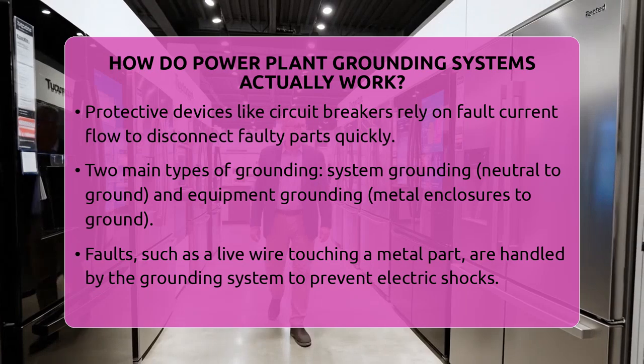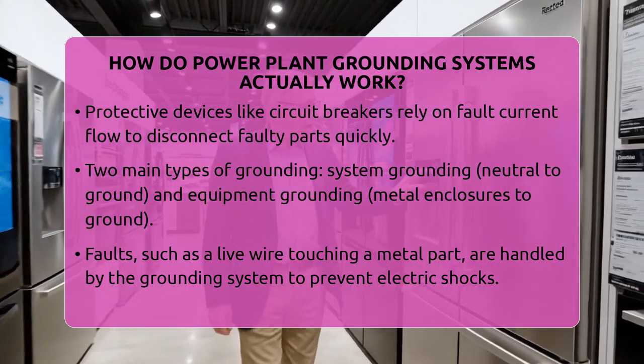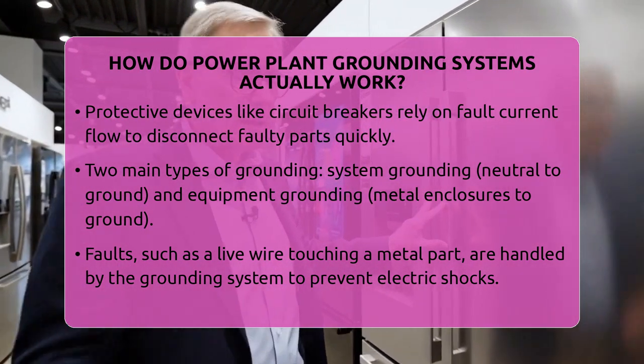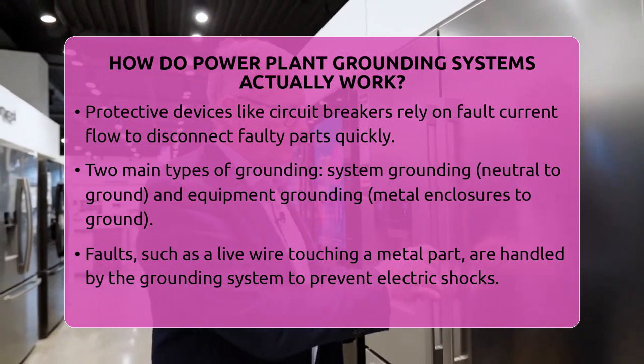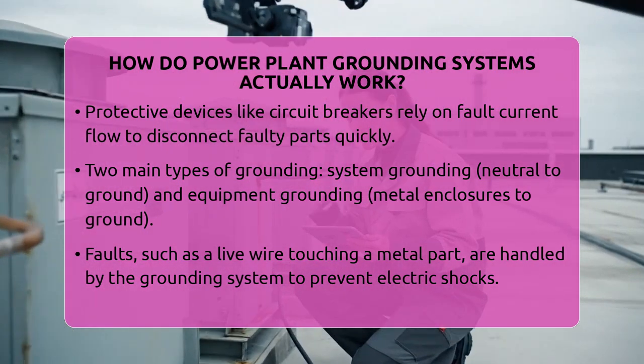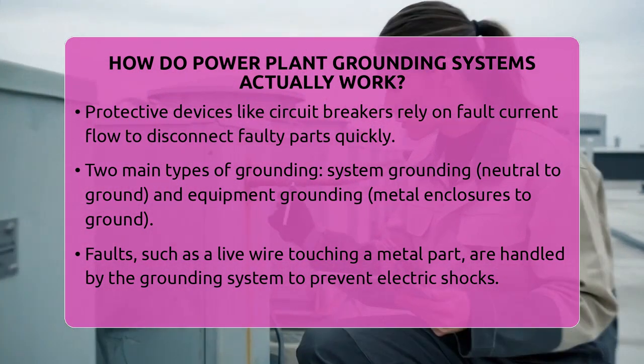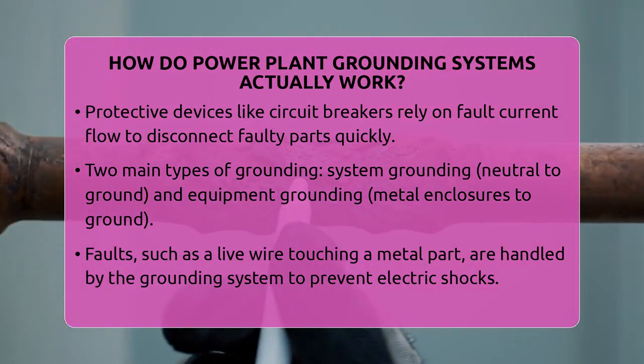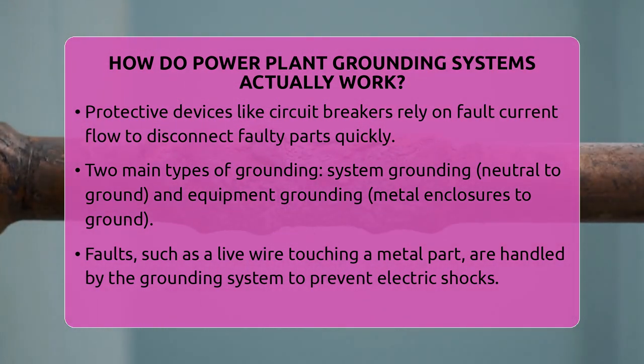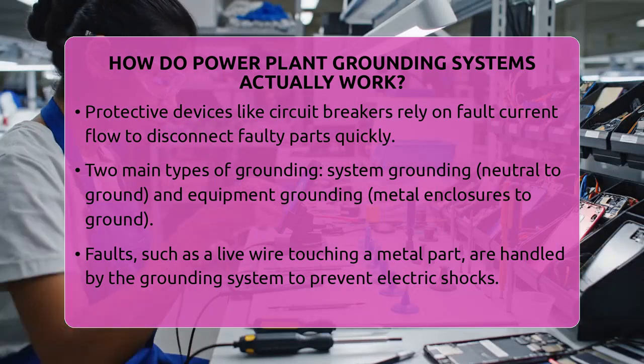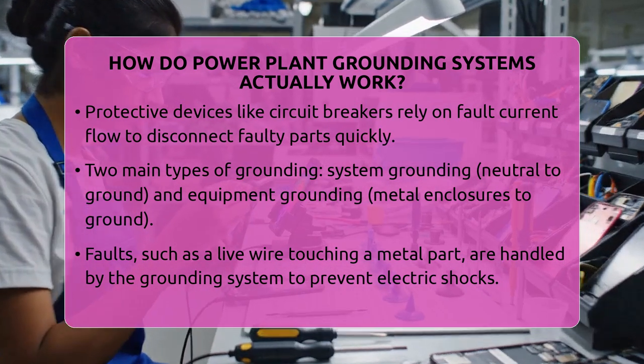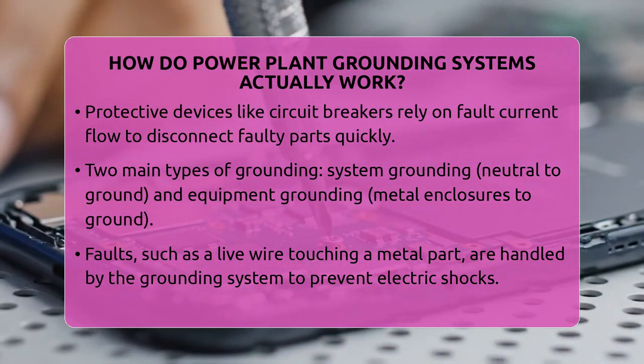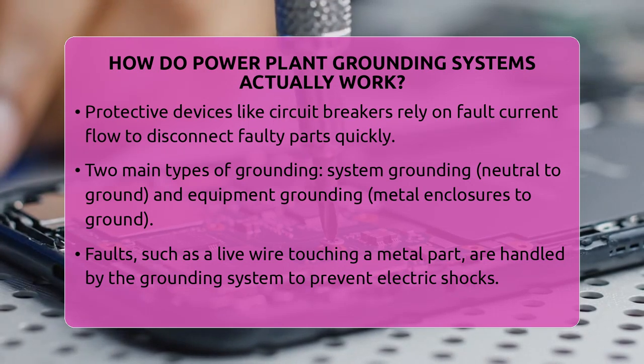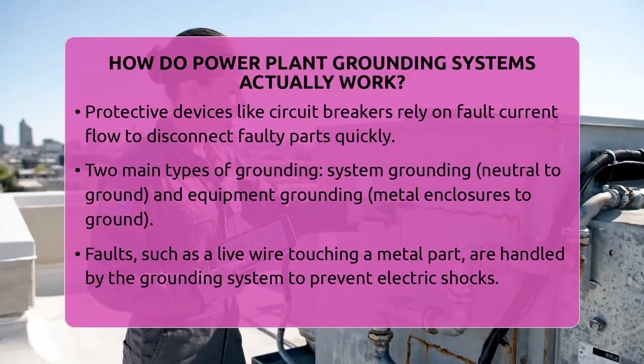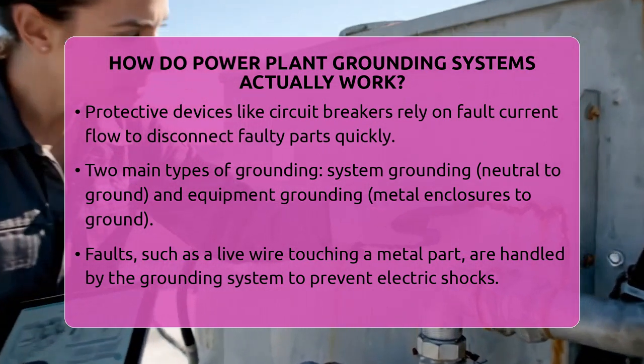When a fault happens, say a live wire touches a metal enclosure, the grounding system provides a low-resistance path for the fault current. This allows the current to flow back to the source quickly. Protective devices sense this surge and trip, isolating the problem. The lower the resistance between the grounding electrode and the earth, the better the fault current can dissipate. Engineers test soil resistivity beforehand to ensure the grounding grid will work effectively.